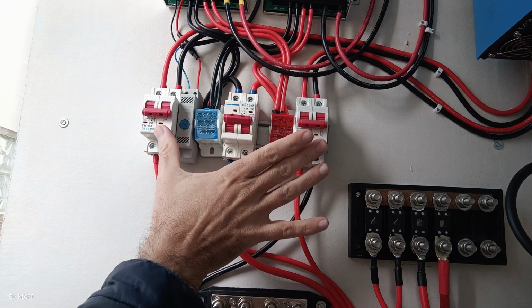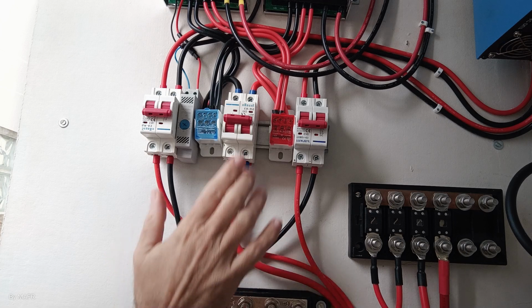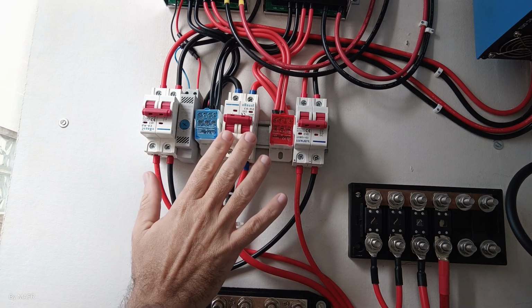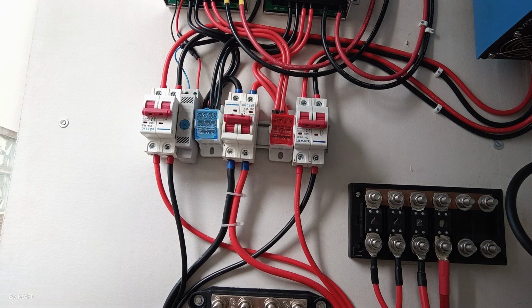From the inverters and the charge controllers, which is this circuit of 63 amperes, they are connected to the bus bars. The bus bars, where I have the battery connected, my battery is 48 volts, 100 amperes maximum. But my system's maximum power here is around 50 amperes peak.